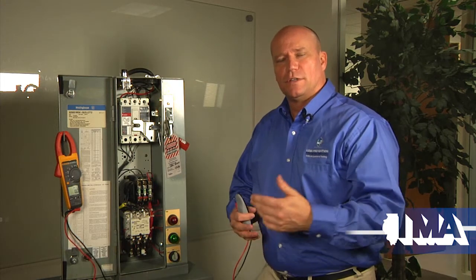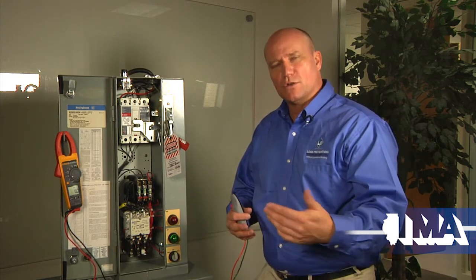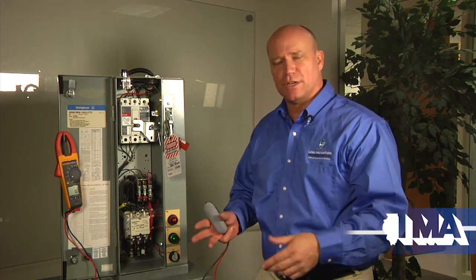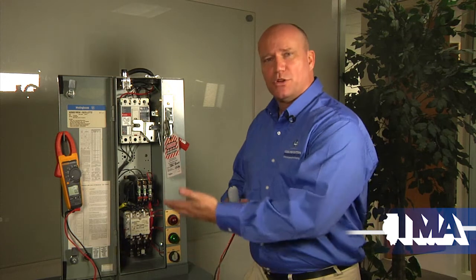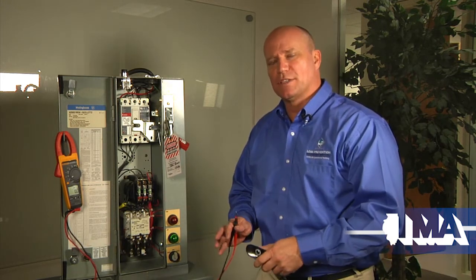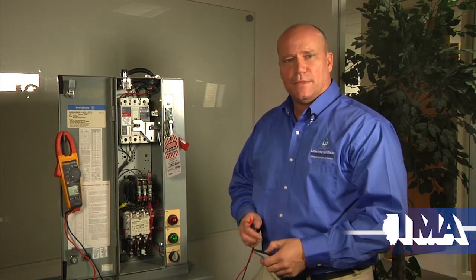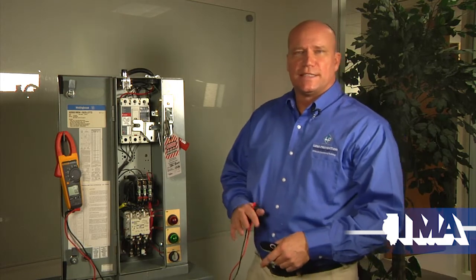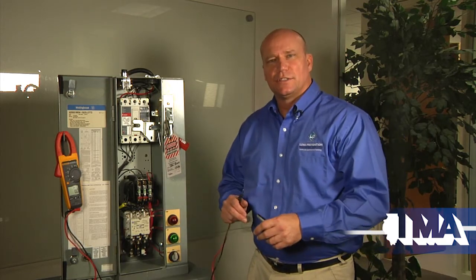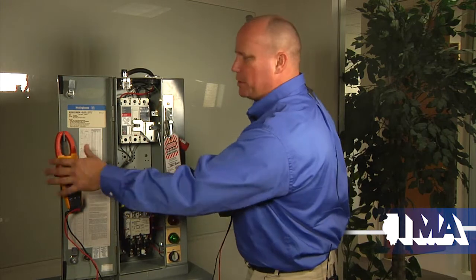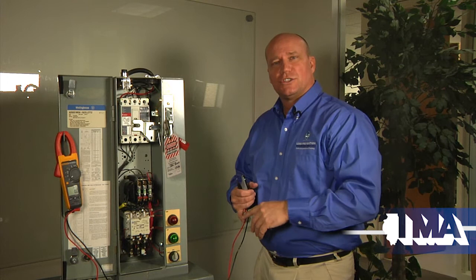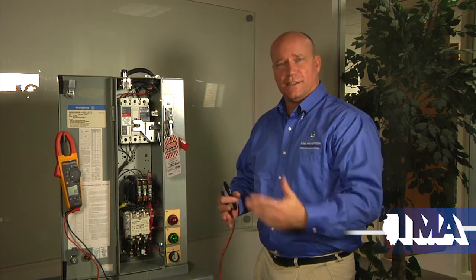Because if there is any differential pressure, and the motor is supplying a fan, the fan could be spinning, and if there's residual magnetism, the requirement for generator action exists, and it could push power back into the system. That would be considered real voltage. It might be a small amount of voltage, but that's something you have to be concerned about. If you get voltage that's verified not magnetically induced, first stop, close up your work, inform supervision, and then investigate the reason.